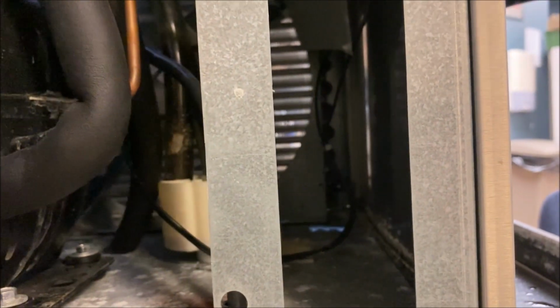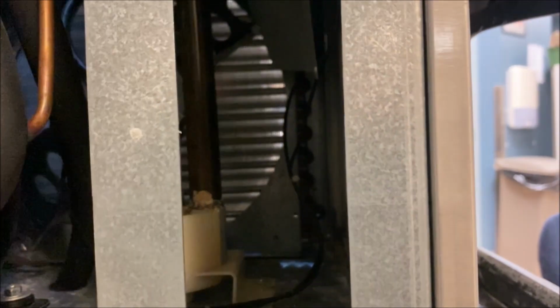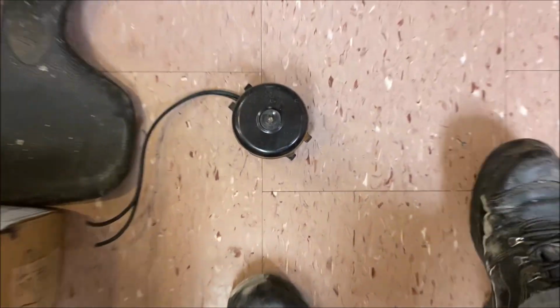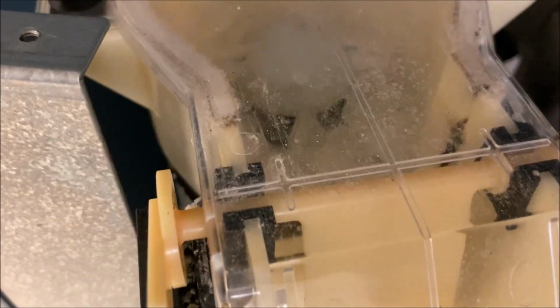Our high pressure switch might still be bad. It might be damaged, but definitely the fan motor's bad. So first thing we're going to do is go ahead and change this fan motor out. And we got the fan motor out. And we'll pop the new one in. And look at that. The fan motor is now running. I don't have to kickstart it. We are not going off on high pressure cutout switch. And we are beginning to make ice. We're dropping into the bin.